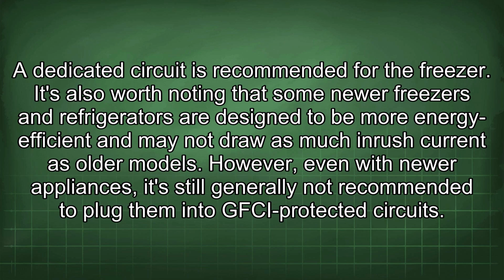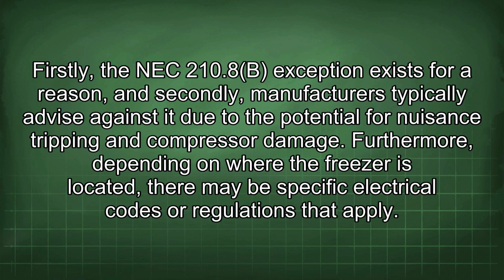However, even with newer appliances, it's still generally not recommended to plug them into GFCI protected circuits. Firstly, the NEC 210.8b exception exists for a reason, and secondly, manufacturers typically advise against it due to the potential for nuisance tripping and compressor damage.